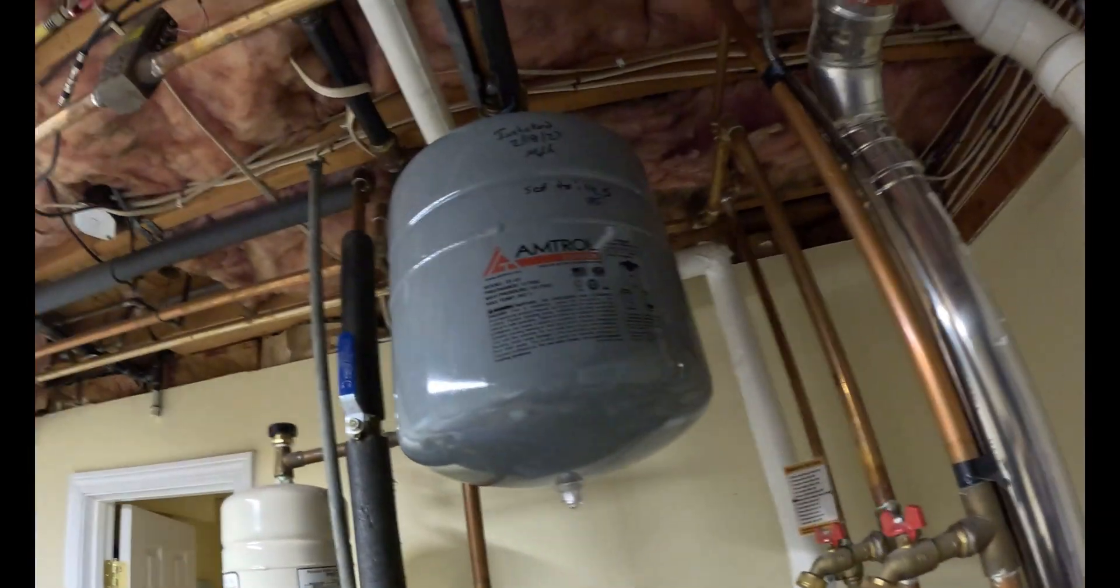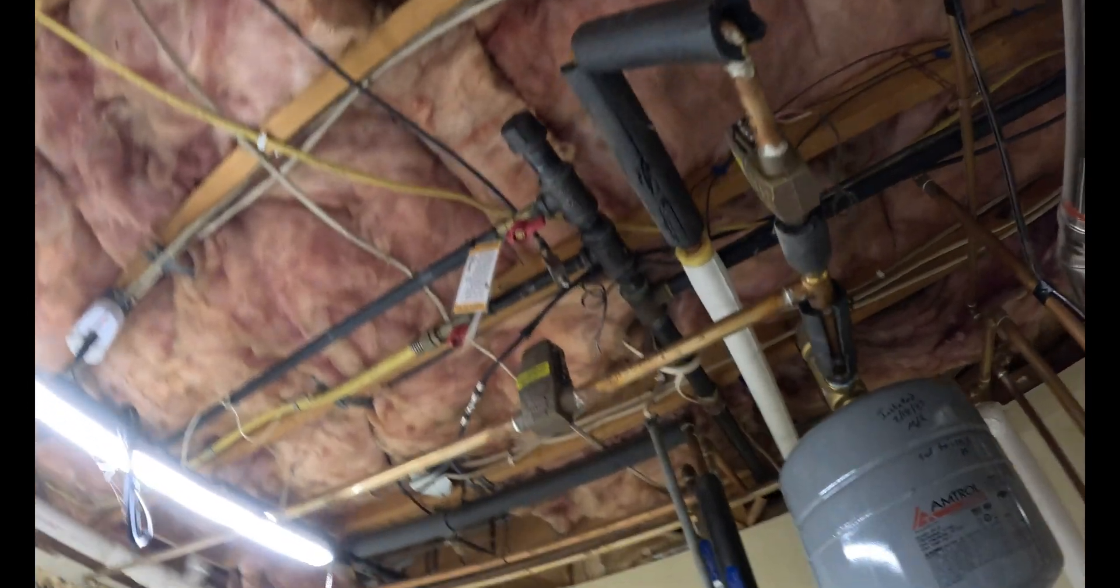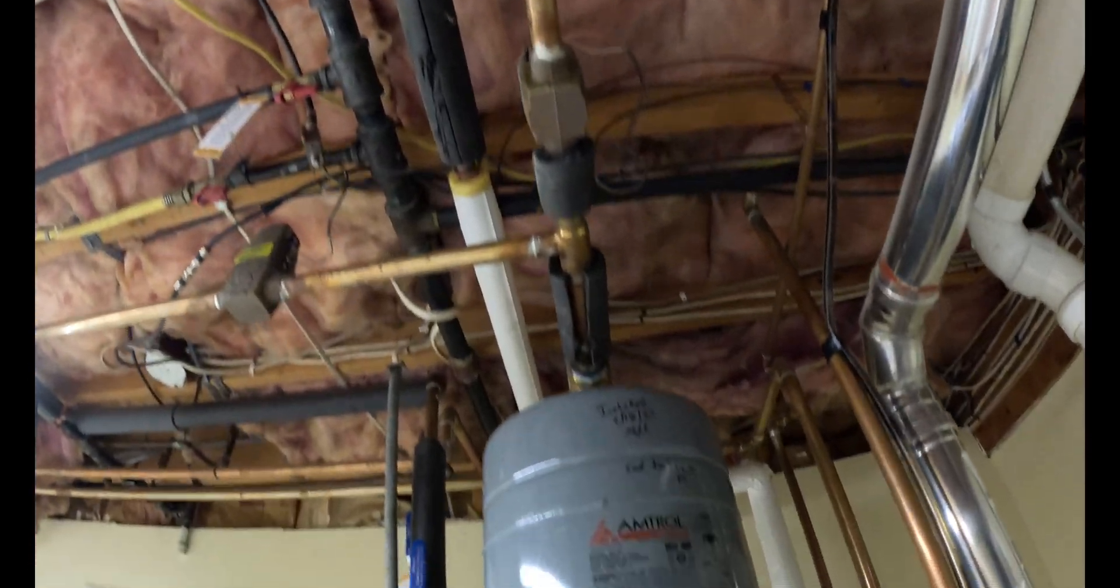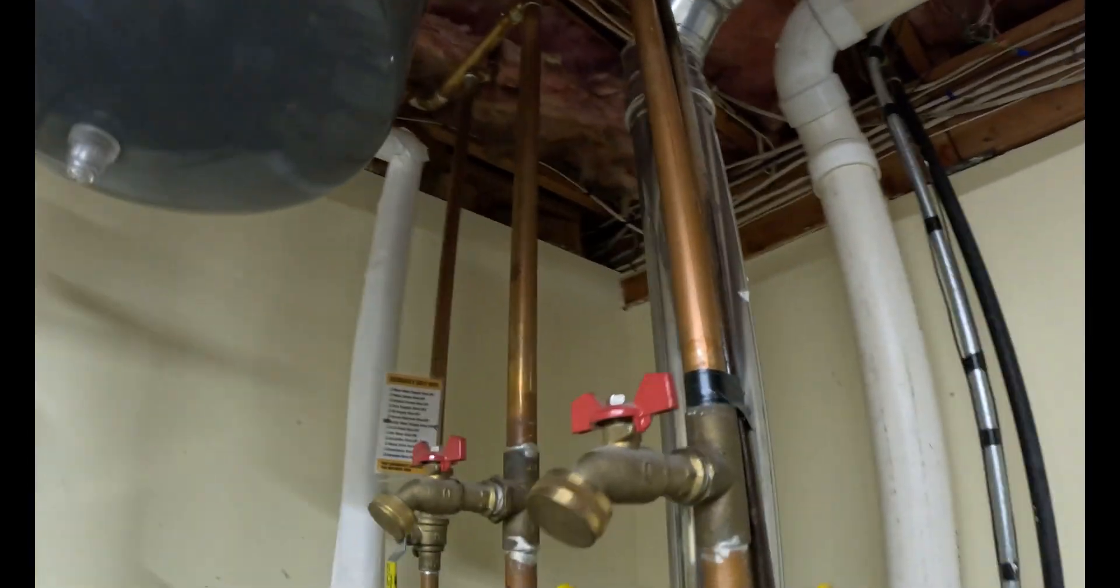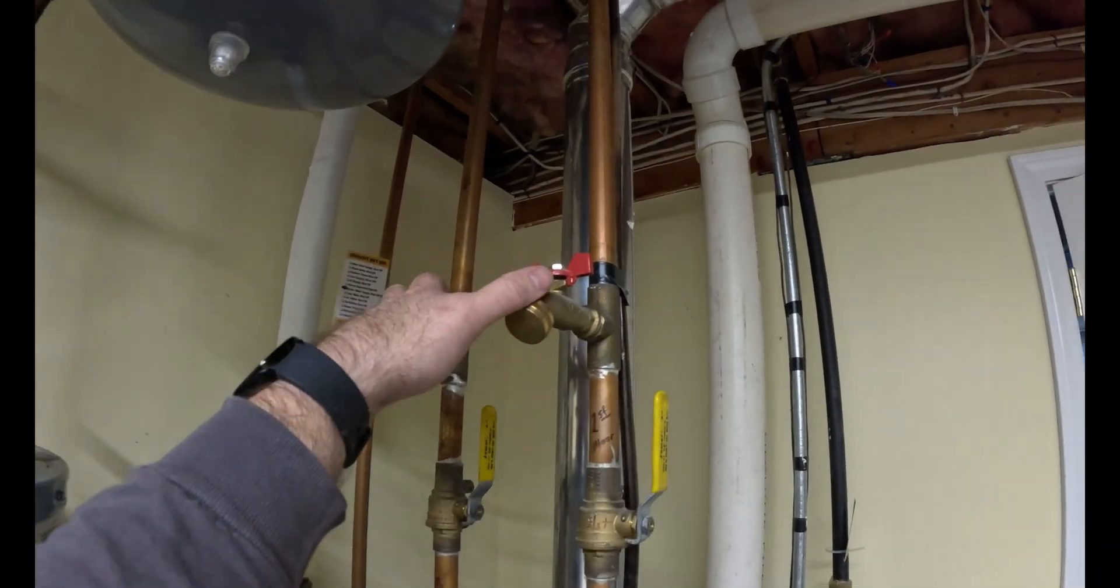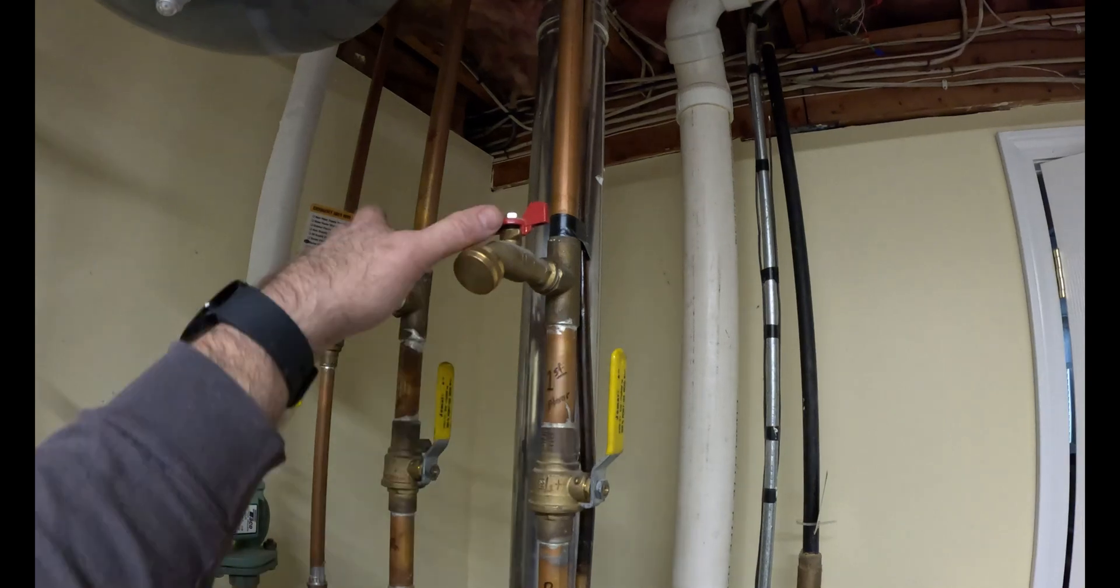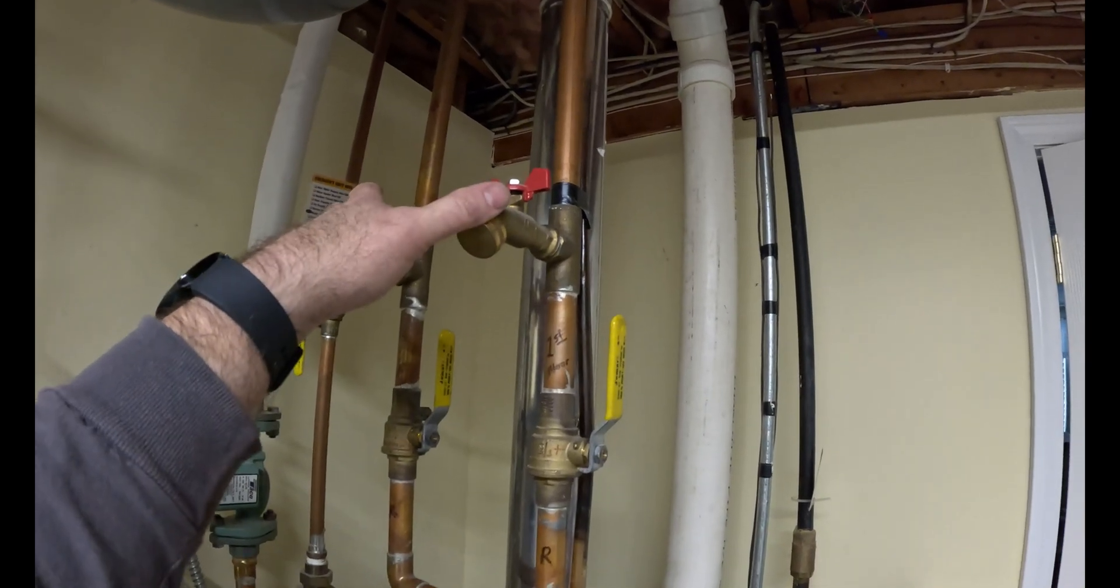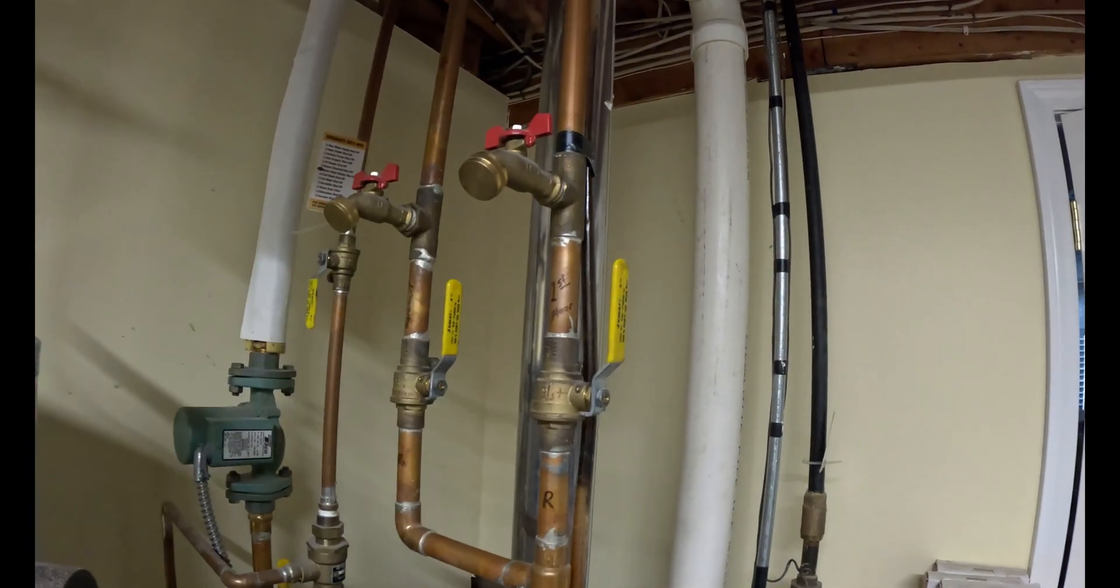Those are our supplies going up and into the house. Down here, our returns come back. Got a nice shutoffs here, purge station so we can purge each zone individually. Caps on the drains so we don't have any drips.